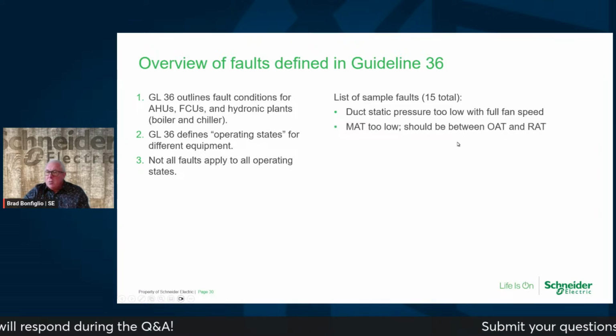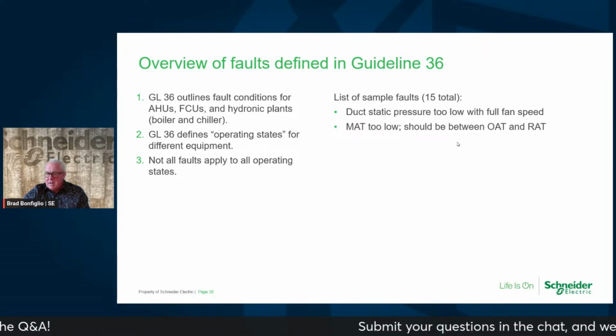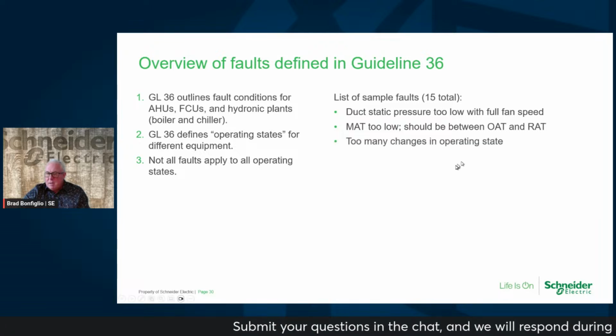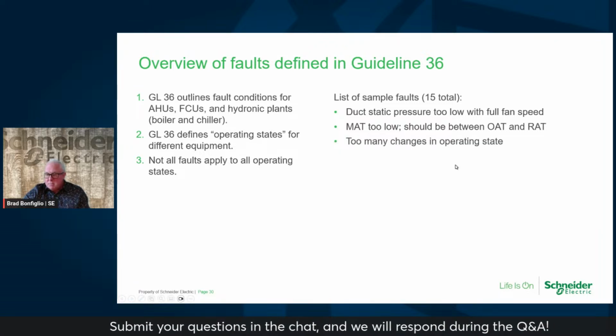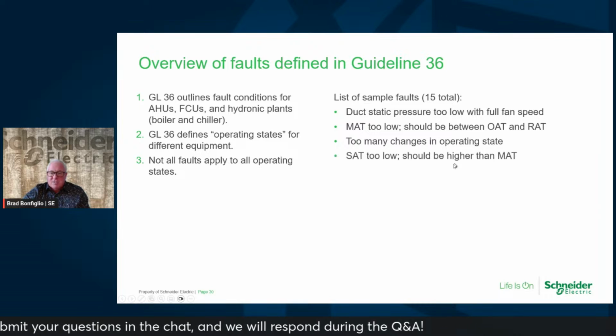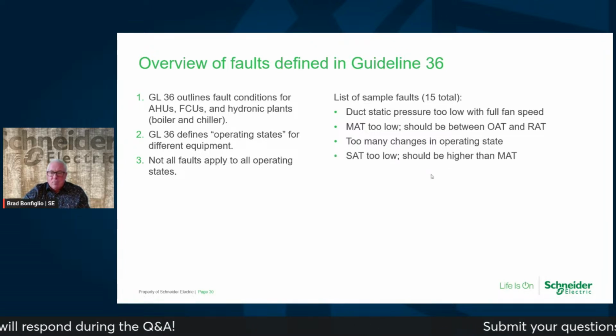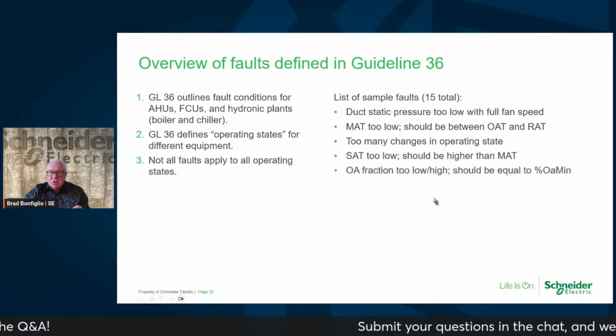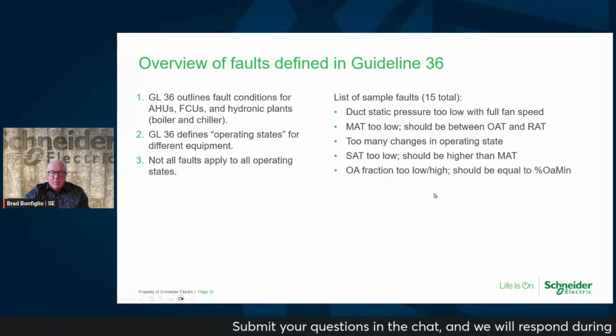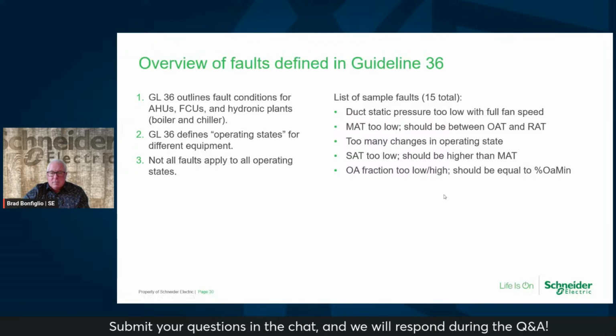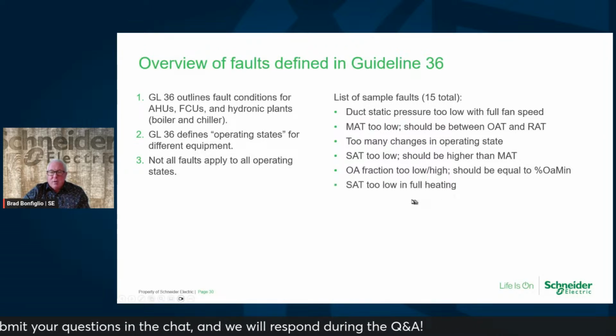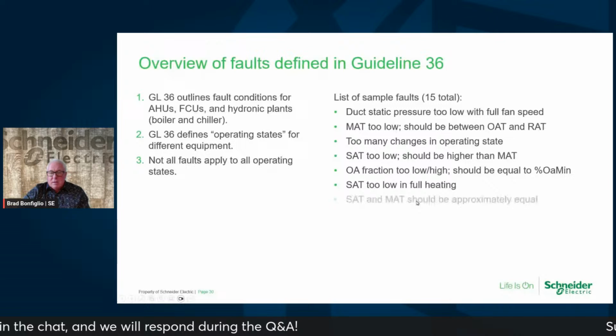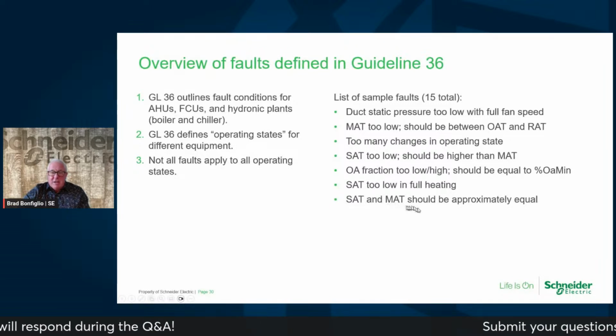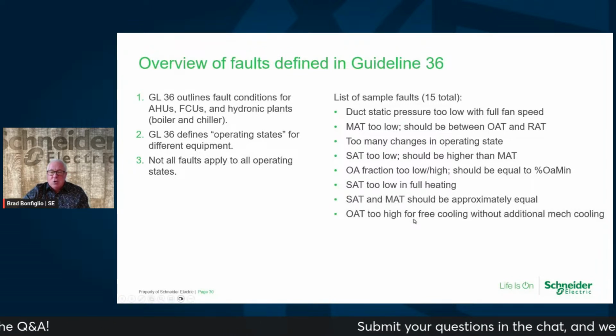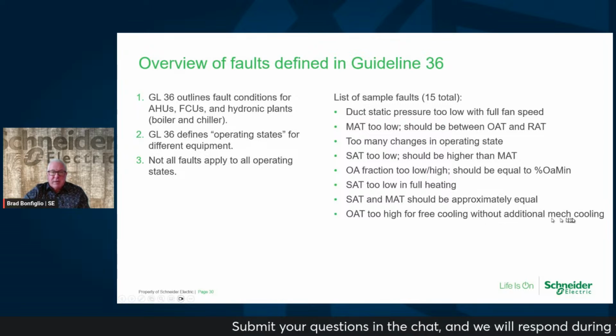Mixed air temp too low. It should be between the outside air temp and the return air temp. Too many changes in operating state, cycling on, off. For example, supply air temperature too low should be higher than the mixed air temp. Outdoor air fraction too high or too low should be equal to the minimum outside air. Supply air temp too low in full heating mode. Supply and mixed air should be approximately equal. Outside air too high for free cooling without additional mechanical cooling.